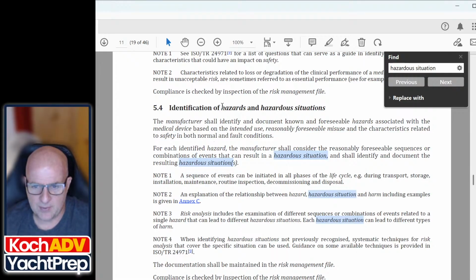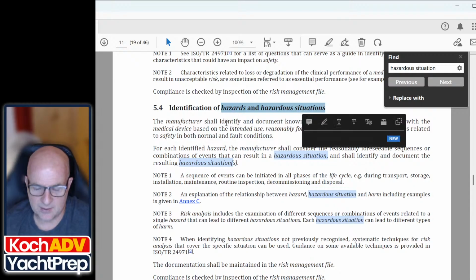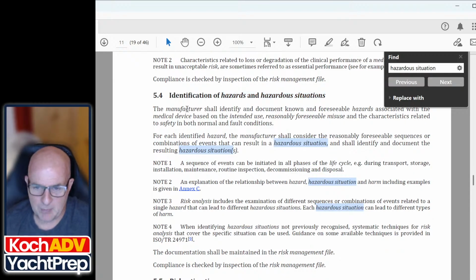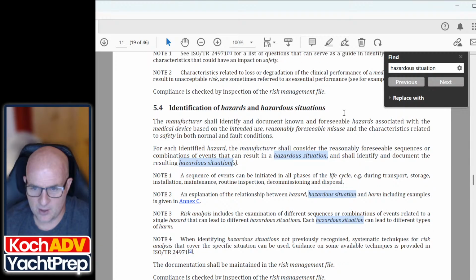So here we go. Identification of hazards and hazardous situations. This is kind of what we started to do. The manufacturer shall identify and document known and foreseeable hazards associated with the medical device based on the intended use, reasonably foreseeable misuse, and the characteristics related to safety.